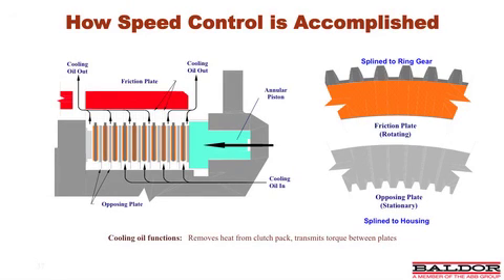As we mentioned, here's an image of the clutch plates. If you look at the black arrow, that's overlaid on top of the actuator piston. That actuator piston is forced in by the positive displacement pump, engaging the clutch plates, and thus engaging the planetary gearbox driving the pump. If you look to the right of the screen, you'll see the friction plate. That's called the rotating plate. And you'll see the diamond pattern in the plates. In those grooves is where the oil flows, and that creates that film barrier that prevents the plates from contacting. The centrifugal pump is what draws the heat away from those clutch plates, cools it through the heat exchanger, and then sends it back.